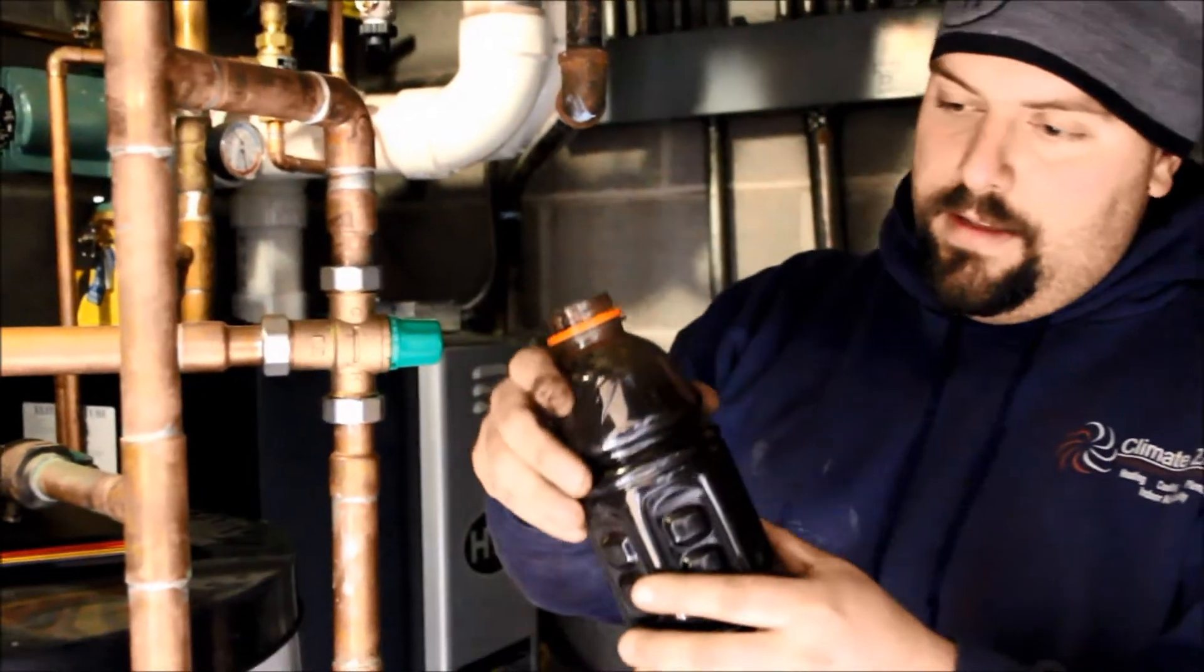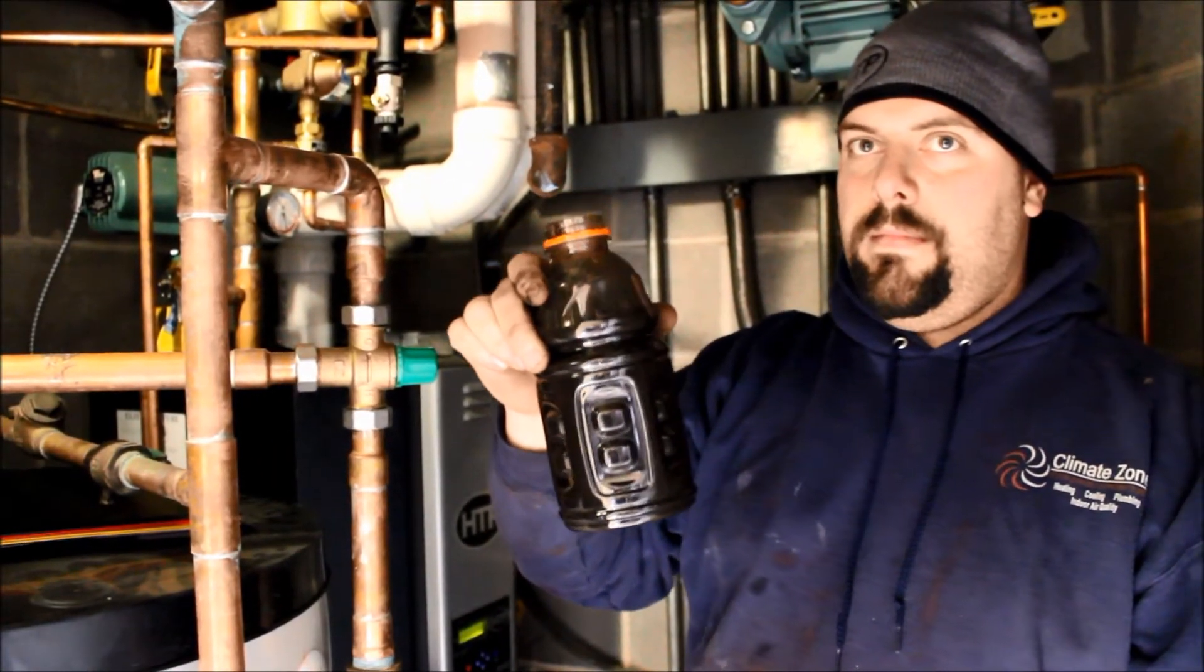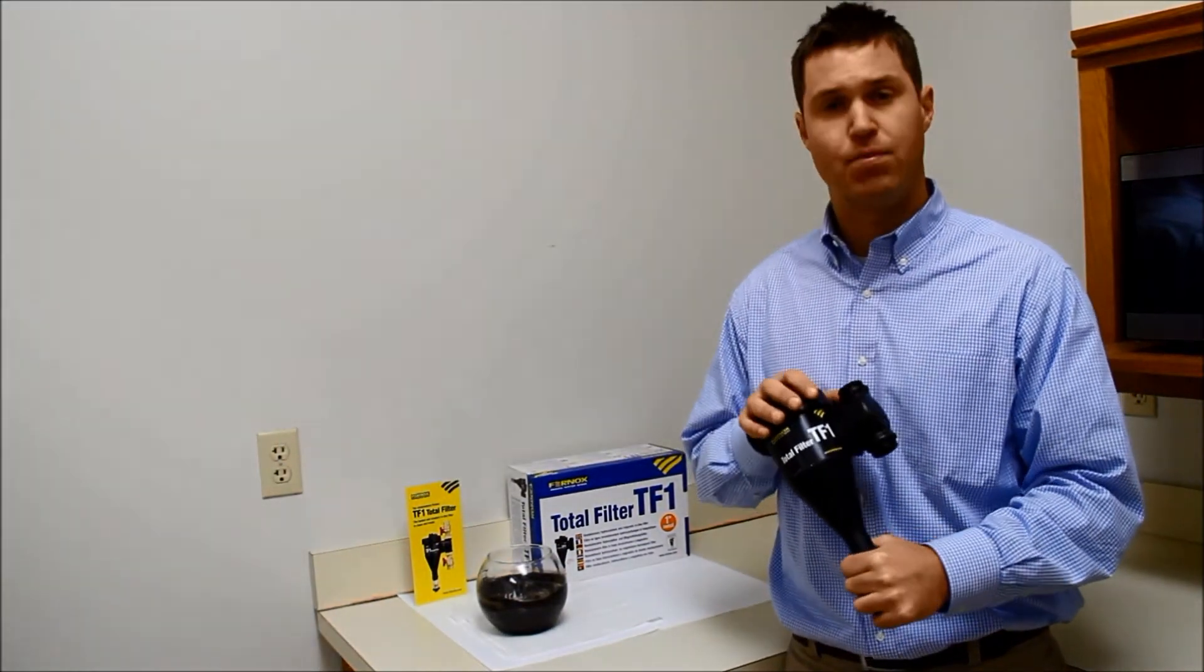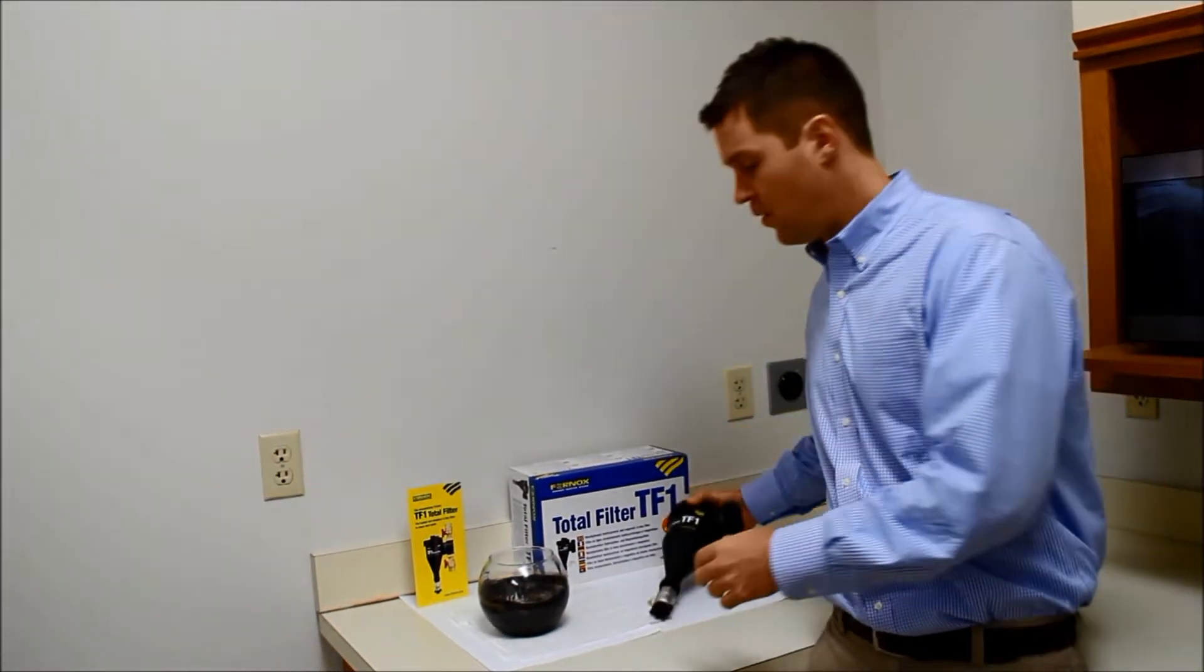And this is what we've collected. So we've just seen Bob empty the TF1 filter out at Plumlee Village and this is what we've come up with. This was just two weeks of this filter in line in the system. So as you can see there's a pretty good amount of sludge and build up that that TF1 collected over the last two weeks.